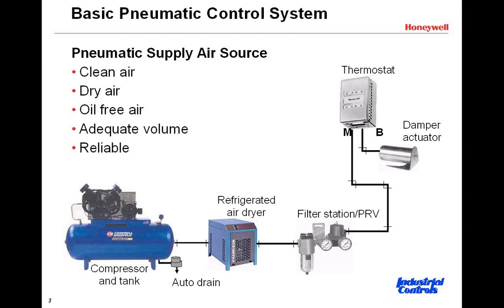Just looking for compressed air pressures on the receiver, listening for sounds, smelling — if you've got belts that are burning or slipping, the motor might hesitate to start the pump. So those kinds of visual checks are really prudent on a daily basis.